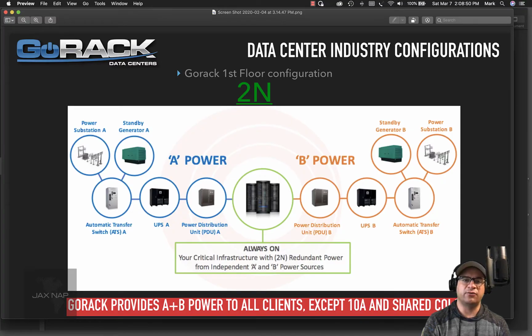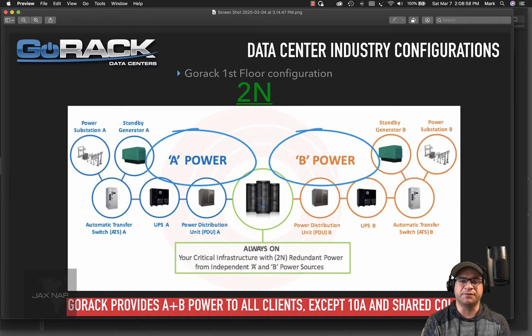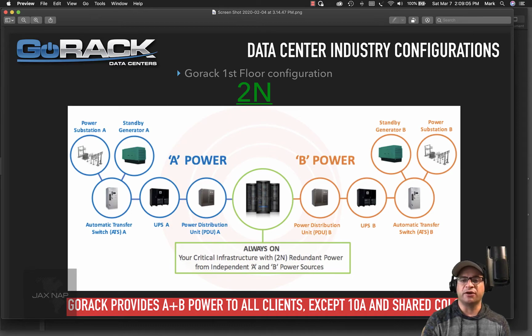After you figured out whether you need 120 volt power or 208 volt power, some data centers are going to give you the option of A plus B configuration. What A plus B configuration means is that if you have an A load that's operational, you're going to have a mirrored B side that's going to mirror the power on the other side. So if you have a failure on one side, let's say on A power, all the power will pick up on B side. So you have to take in consideration you might need 2 PDUs for each cabinet.